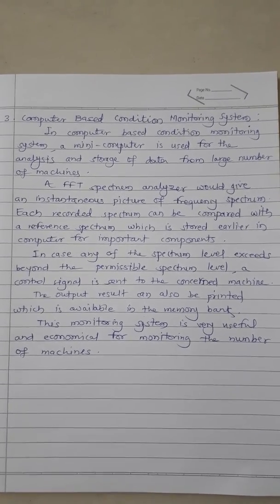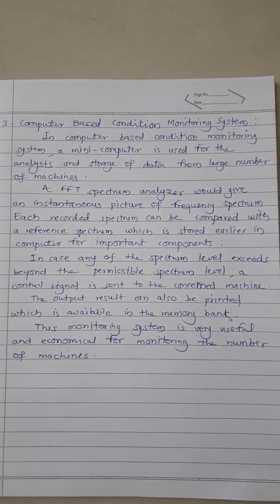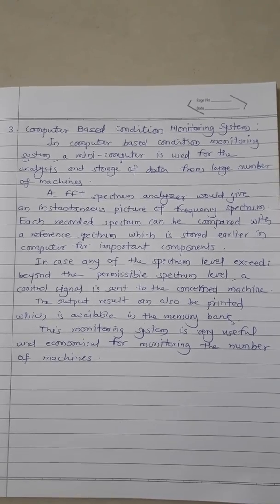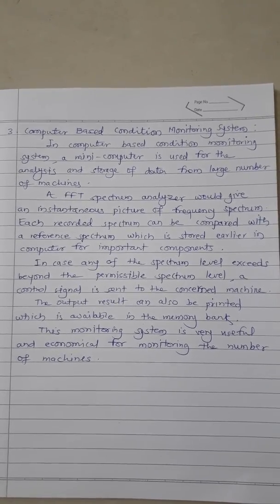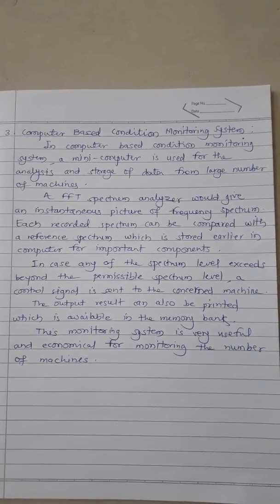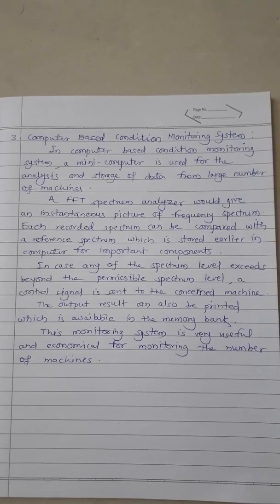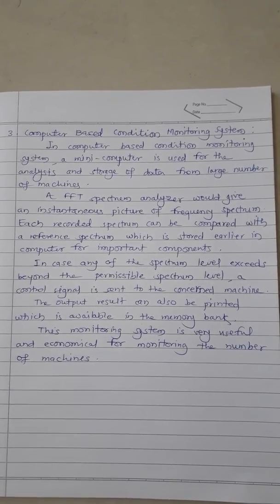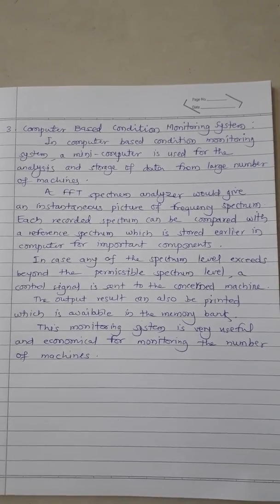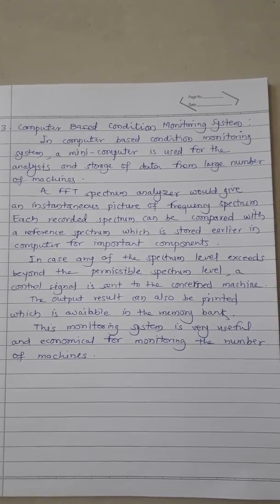Computer-based condition monitoring system: in this system, a mini-computer is used for the analysis and storage of data from a large number of machines. An FFT spectrum analyzer gives an instantaneous picture of the frequency spectrum. Each recorded spectrum can be compared with a reference spectrum stored earlier in the computer. For important components, if any spectrum level exceeds beyond the permissible level, a control signal is sent to the machine. The output results can also be printed and are available in the memory bank. This monitoring system is very useful and economical for monitoring a large number of machines.